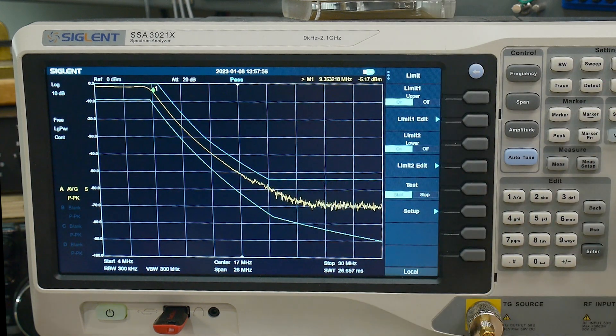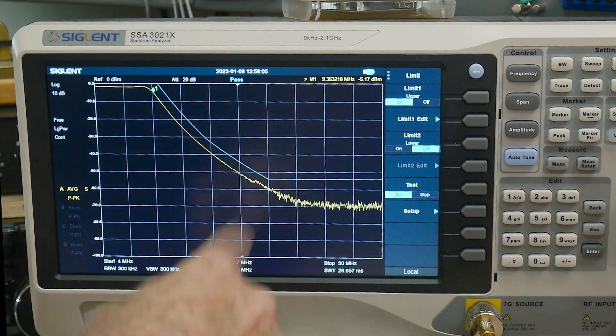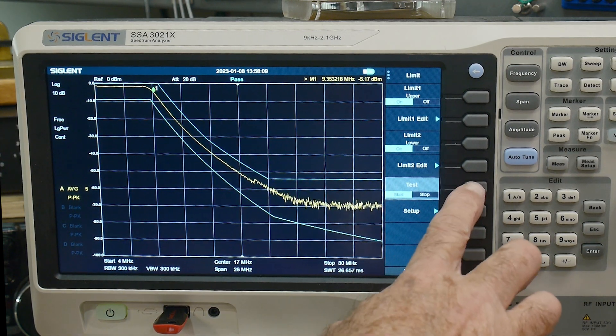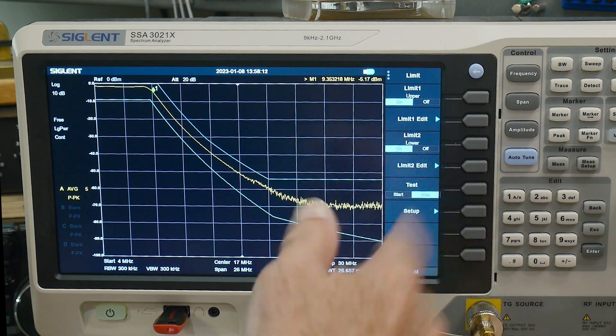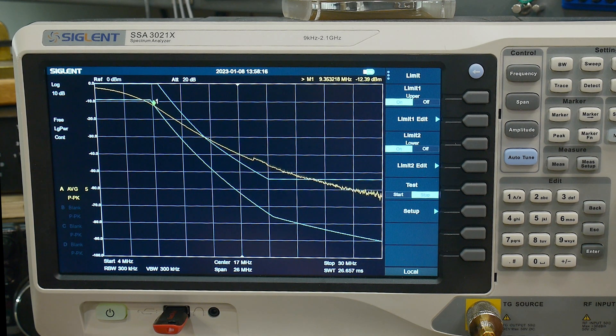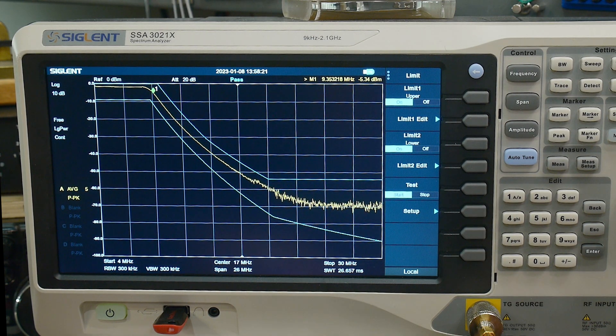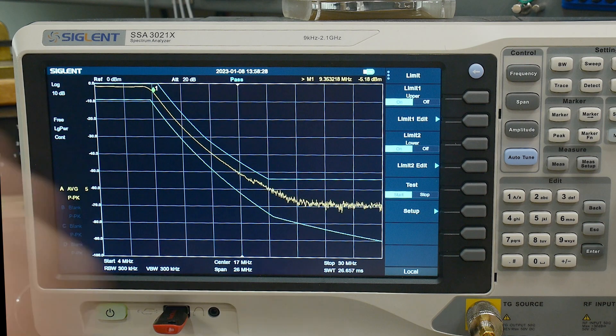The limits button gets you to this menu. You can have an upper limit and a lower limit. You can turn the upper limit off and just have a lower limit, or just have an upper limit with no lower limit, or have both limits. There's also a start and stop — if you have it in stop, it won't warn you when you go out of bounds, but if the test is on, it will go back into the fail condition.